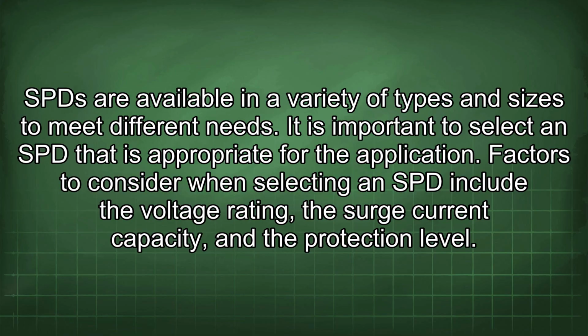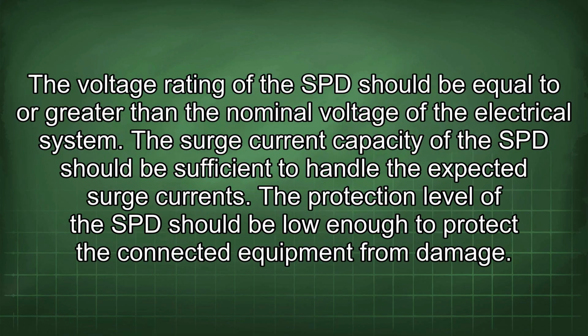Factors to consider when selecting an SPD include the voltage rating, the surge current capacity, and the protection level. The voltage rating of the SPD should be equal to or greater than the nominal voltage of the electrical system. The surge current capacity of the SPD should be sufficient to handle the expected surge currents. The protection level of the SPD should be low enough to protect the connected equipment from damage.